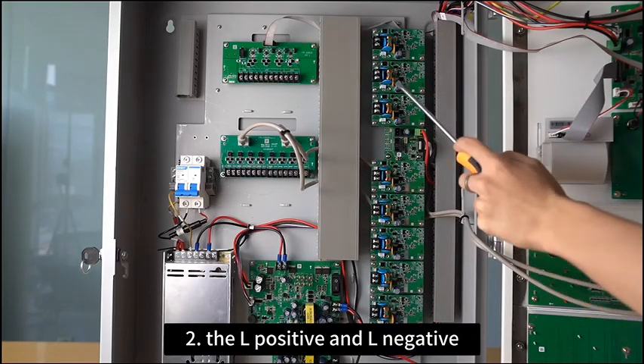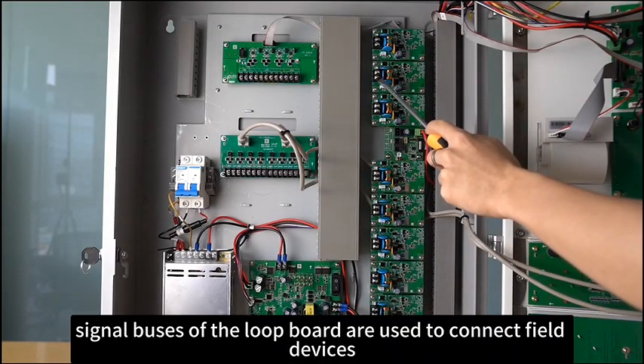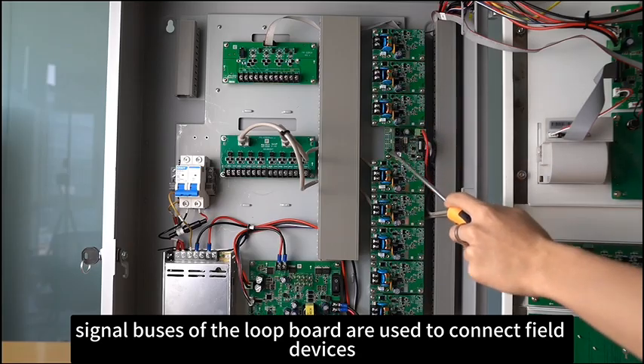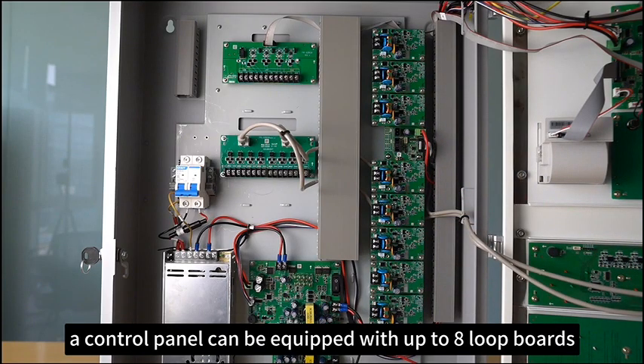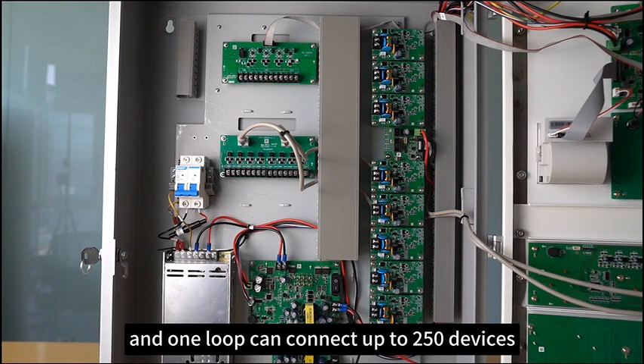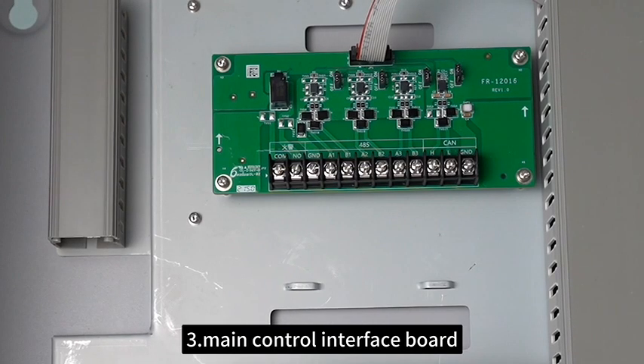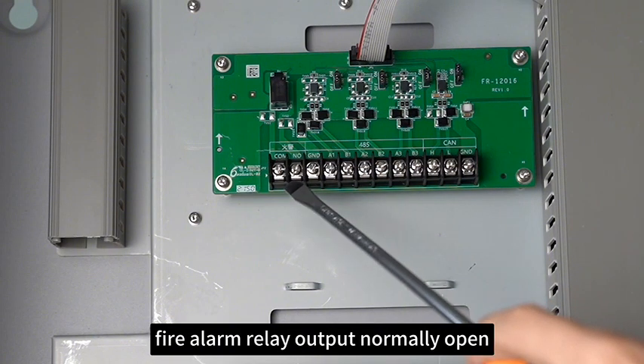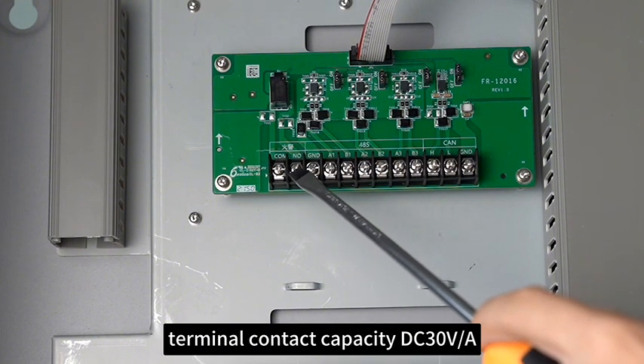Second, the L-positive and L-negative signal buses of the loop board are used to connect field devices. A control panel can be equipped with up to 8 loop boards, and one loop can connect up to 250 devices.